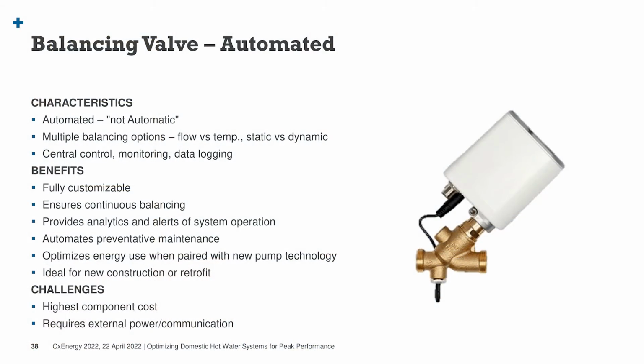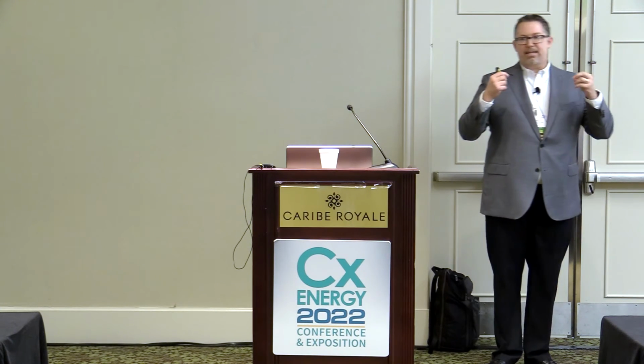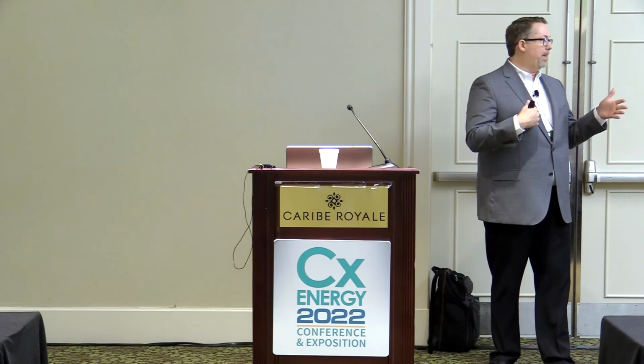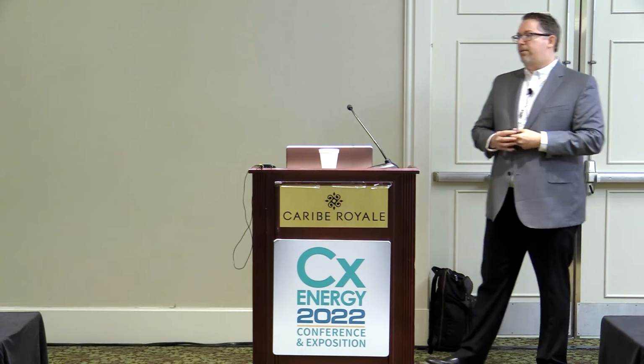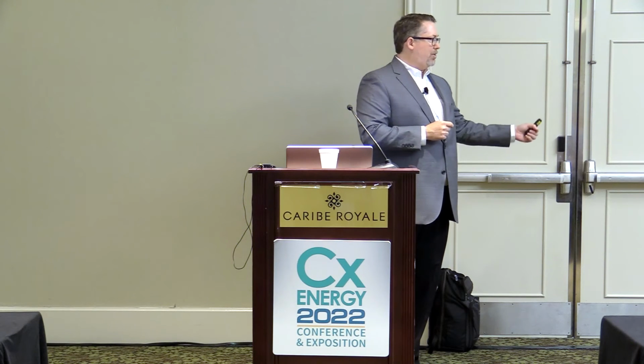And then on the automated side, as I mentioned, there's a difference between an automatic and an automated. Automatic, there is a physical response to a change, right? Whether it's the pressure independent type, it's responding to pressure changes just in a physical environment. Same with the thermostatic. It's not intelligent in the sense that it is just wax expanding or contracting based on temperature. That calibration had to have happened at the factory. With an automated valve, it is actually gathering data, and that data is being used to make a decision for that valve. So it's a more intelligent way for that valve to respond and to react.